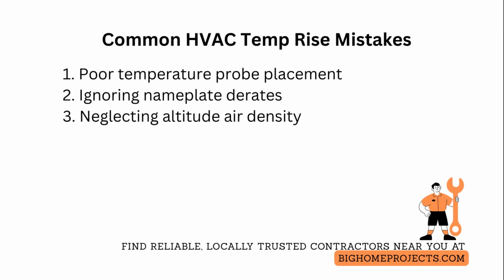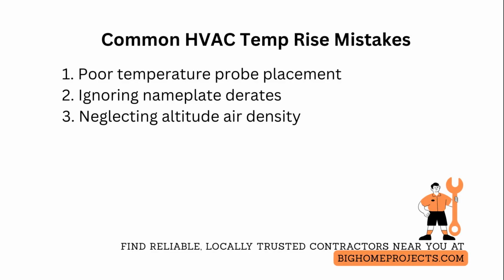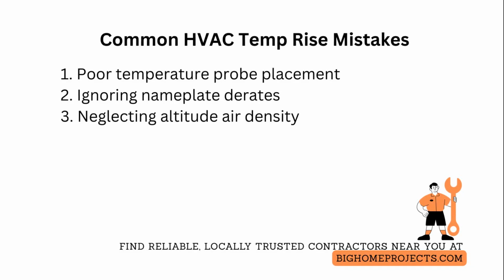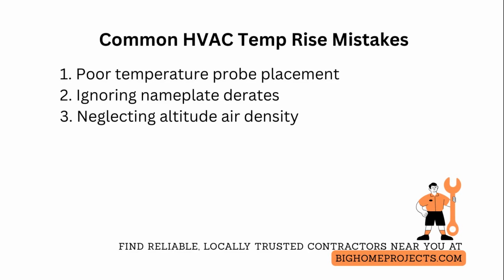One of the top mistakes is poor temperature probe placement, causing inaccurate CFM and temperature rise readings. Fix it by mounting probes with spring clips inside the center third of the duct and averaging 3 cross-sectional points.